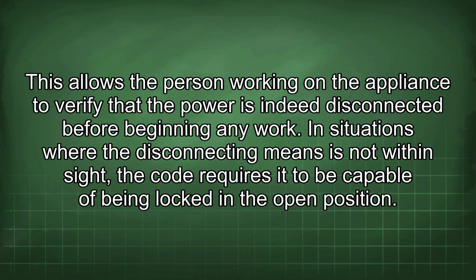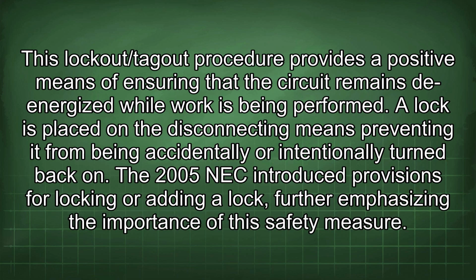The within sight requirement means that the disconnecting means must be visible and within 50 feet from the appliance. This allows the person working on the appliance to verify that the power is indeed disconnected before beginning any work. In situations where the disconnecting means is not within sight, the code requires it to be capable of being locked in the open position. This lockout/tagout procedure provides a positive means of ensuring that the circuit remains de-energized while work is being performed.